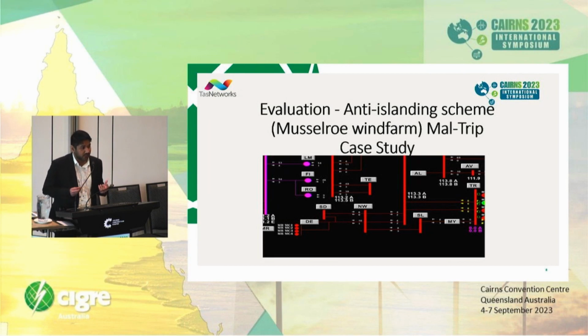What we are doing is we have installed a synchro vector processor. It's taking the input data from both of the PMUs and calculates the voltage slip. If our network gets desynchronized, that means there will be a voltage angle shift at Derby, and we'll just trip off the wind farm. So this is how we are implementing the anti-islanding scheme.